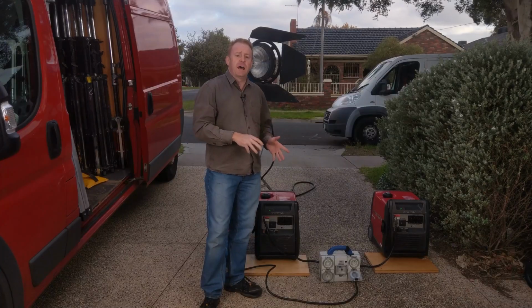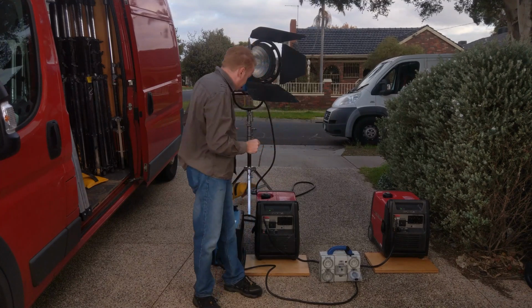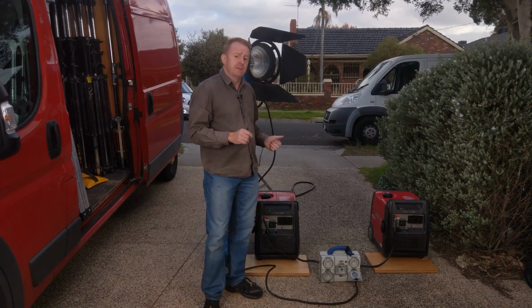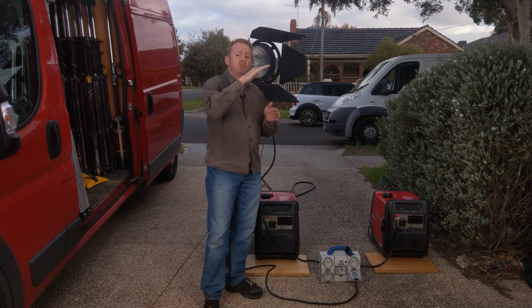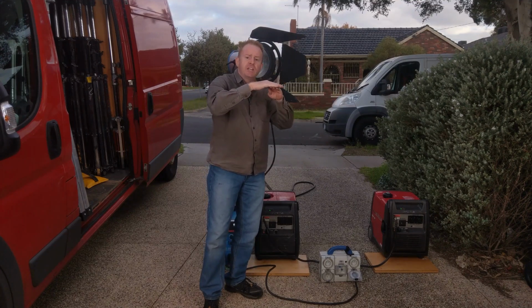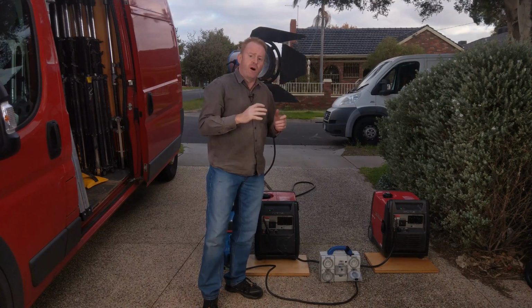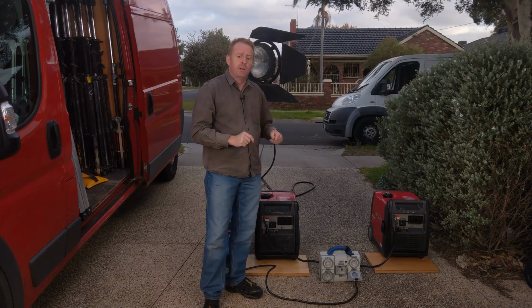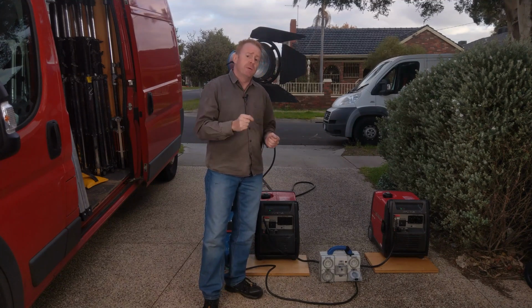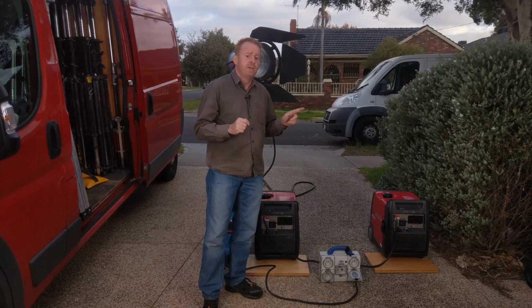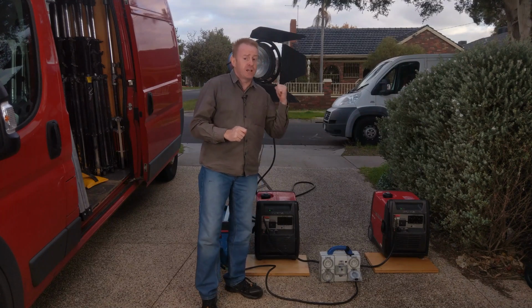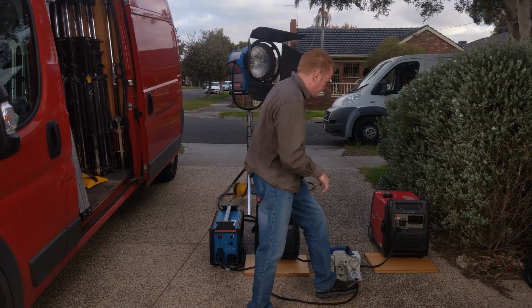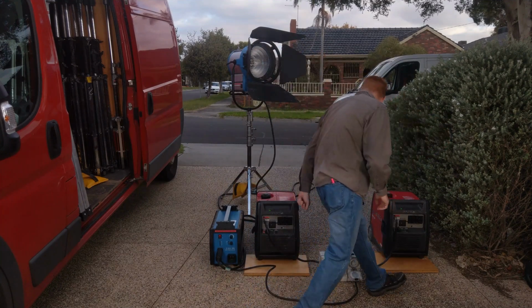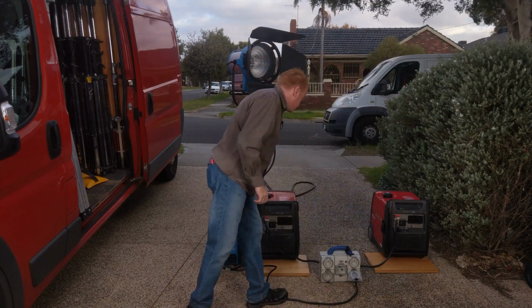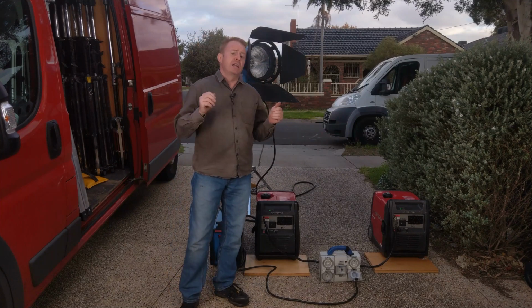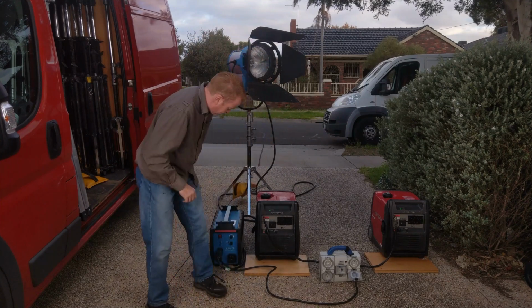Now, before we start up, there's one more issue, and that is how this HMI fires up. So this one's going to slowly go up to 2.5K, and then it's going to jump to 4K. So if I leave these things in eco throttle, they could stall. So I've got to make sure I turn the eco throttle off on both the generators before I start up the HMI. Okay, now I'm ready to start the HMI up.